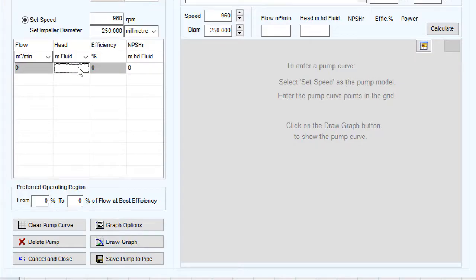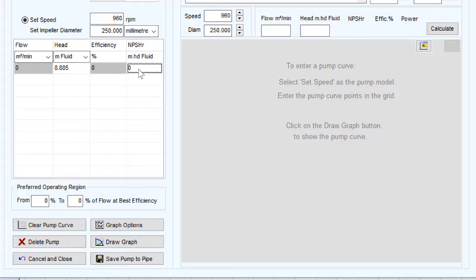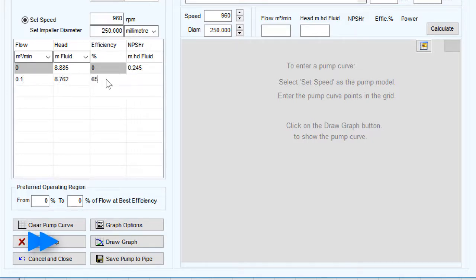Once we have determined the flow points that we wish to include from the manufacturer's pump we can begin to enter the head efficiency and NPSHR values for each of these in the pump data performance table.